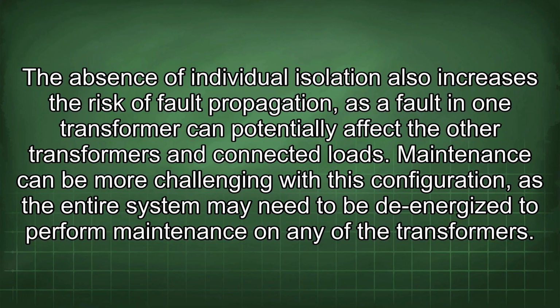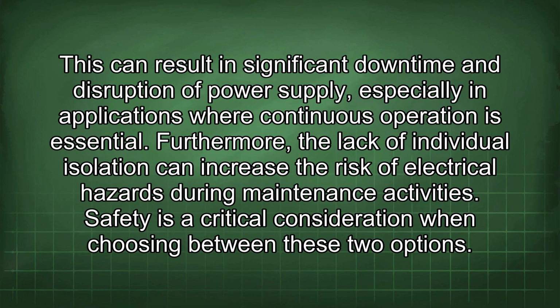Maintenance can be more challenging with this configuration, as the entire system may need to be de-energized to perform maintenance on any of the transformers. This can result in significant downtime and disruption of power supply, especially in applications where continuous operation is essential. Furthermore, the lack of individual isolation can increase the risk of electrical hazards during maintenance activities.